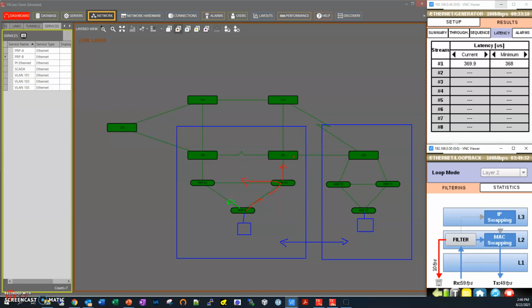Now the MPLS device here for the wide area network will actually take this packet, send it across down here, across the wide area network, inter-substation, and send it right back down there to this HSR PRP gateway. That's going to take this packet and then again send two copies, because remember the destination is that reflector down there that you see right here. And the same thing happens on the other side.